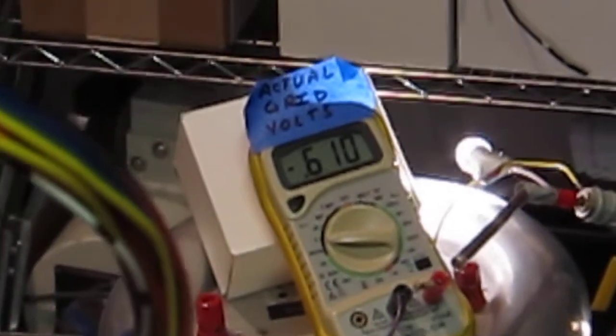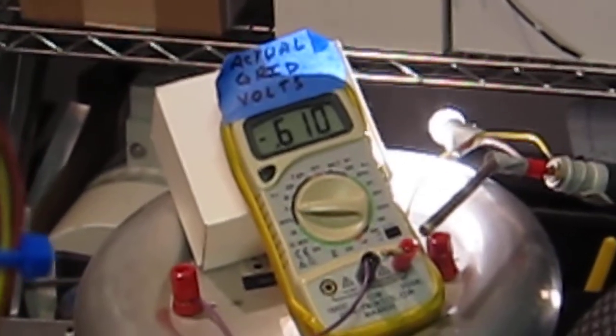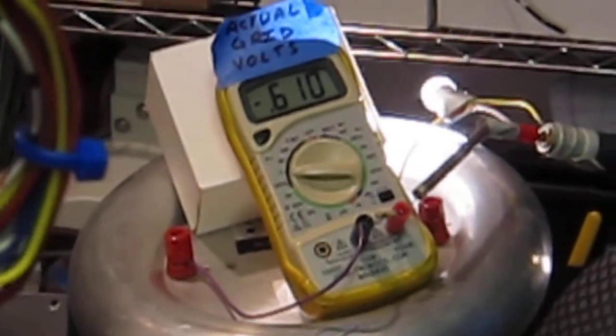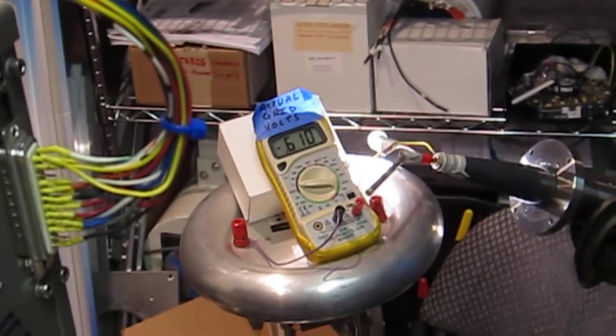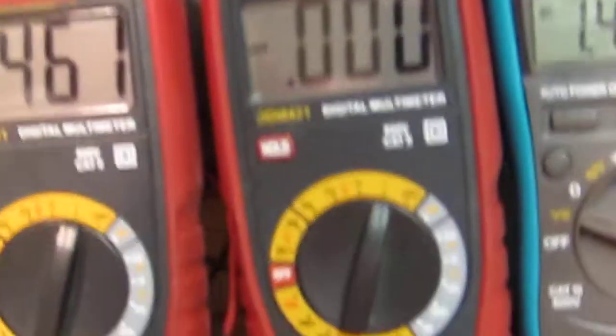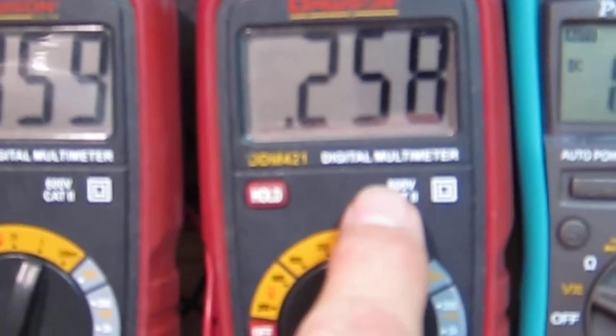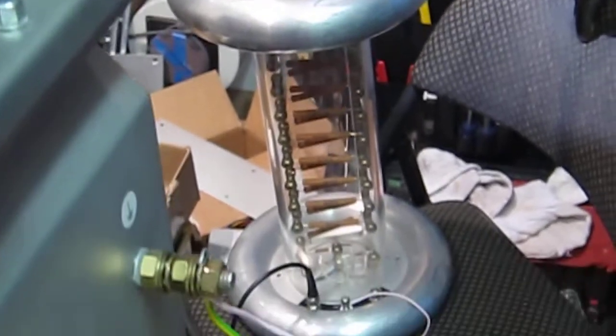Okay, and it's not going to have proper servo control, I'll say again, because there is not a true X-ray tube that's going to change the tube current. And if I enable the tube current, it says that I have 258 microamps through the X-ray tube, and that's basically current flowing through that resistor, through the metering resistor that's being read here at 20.6 kilovolts.